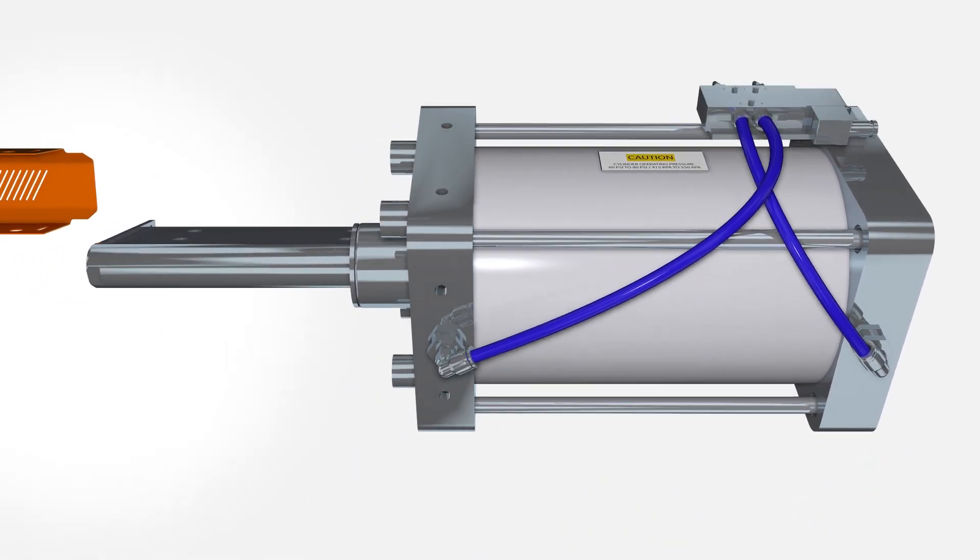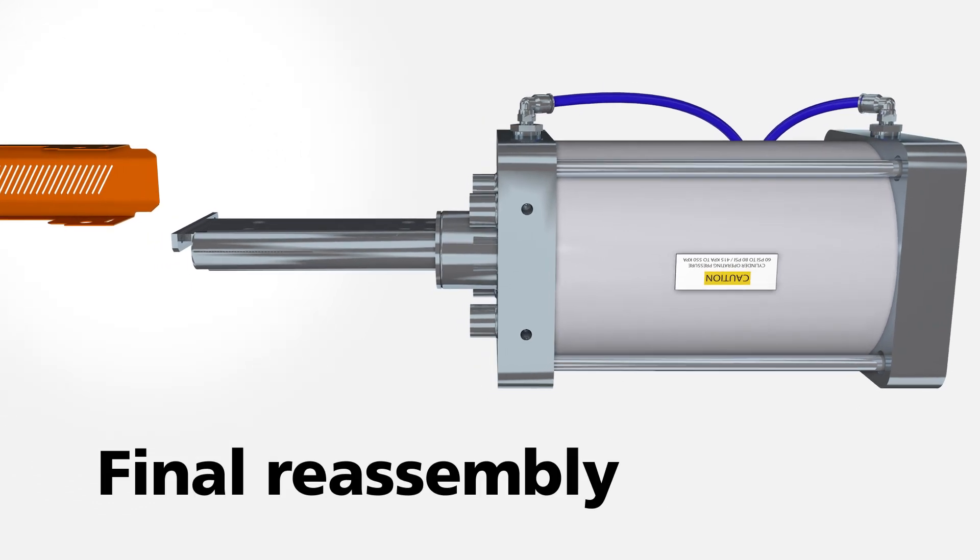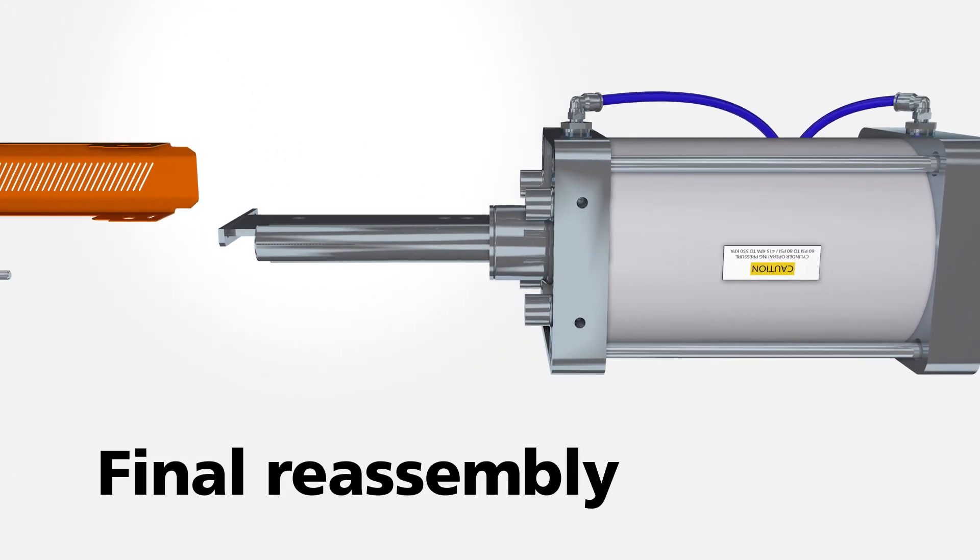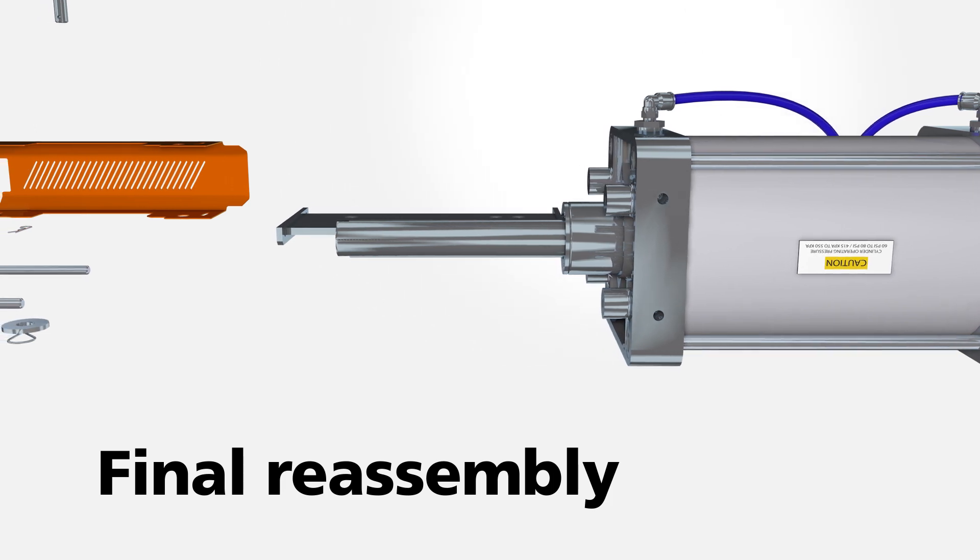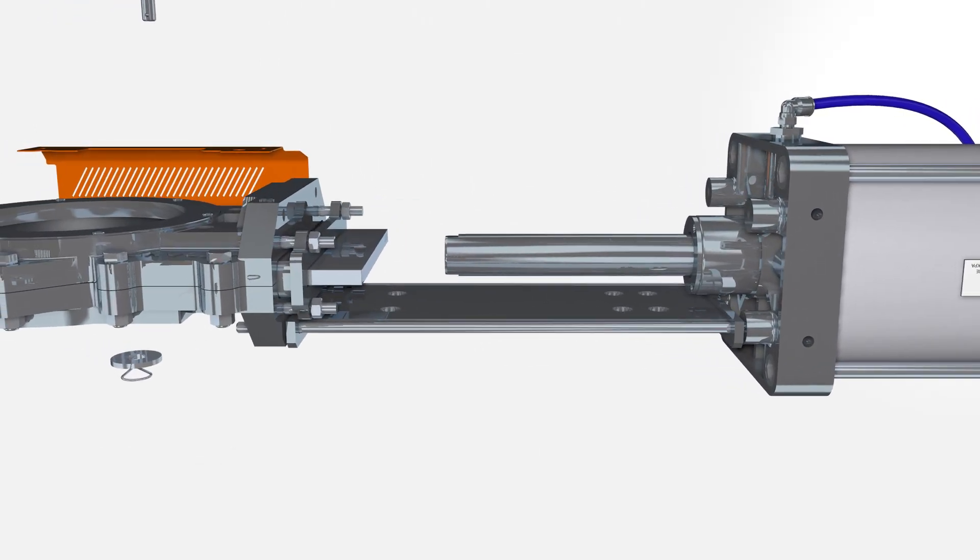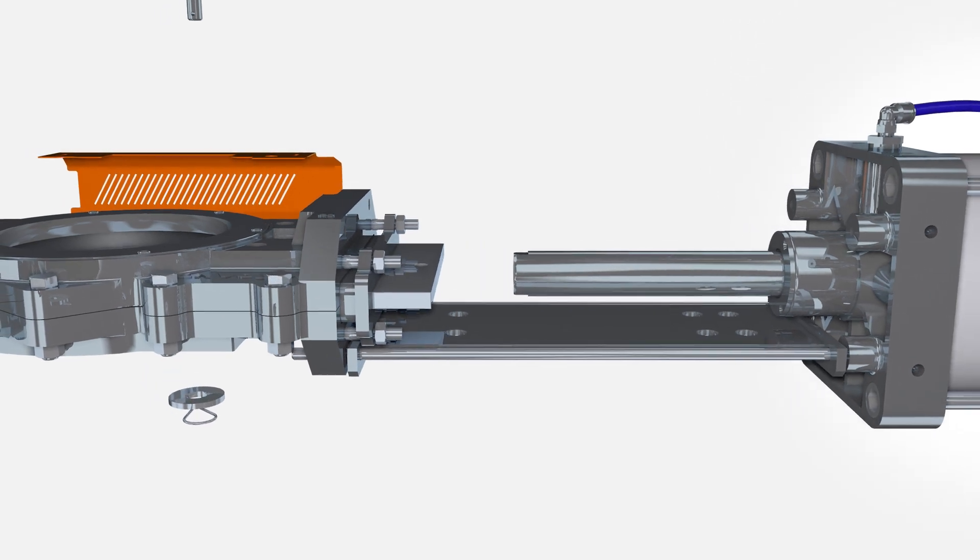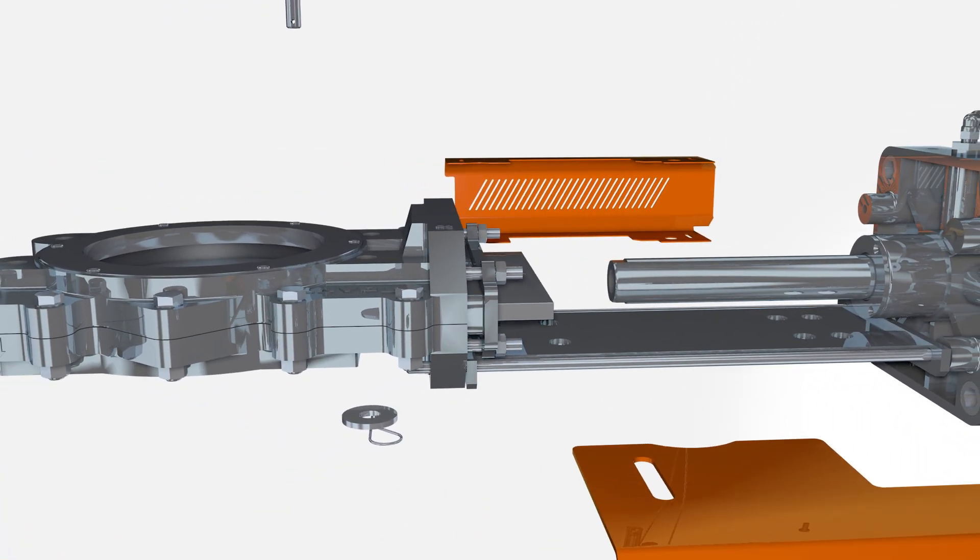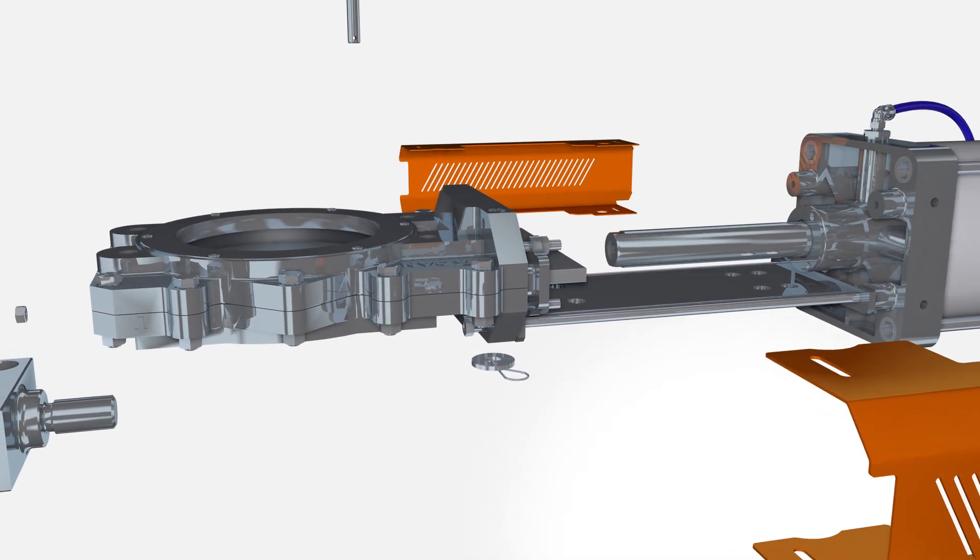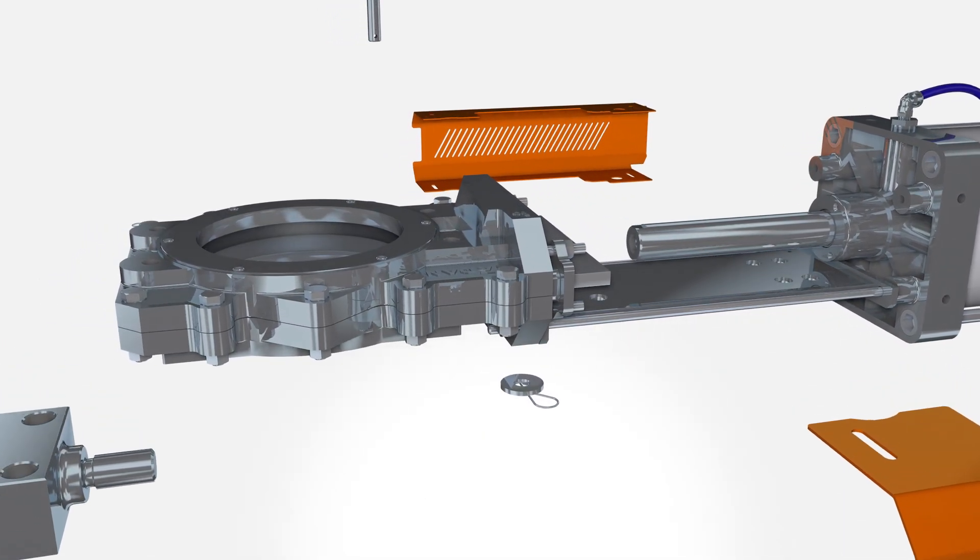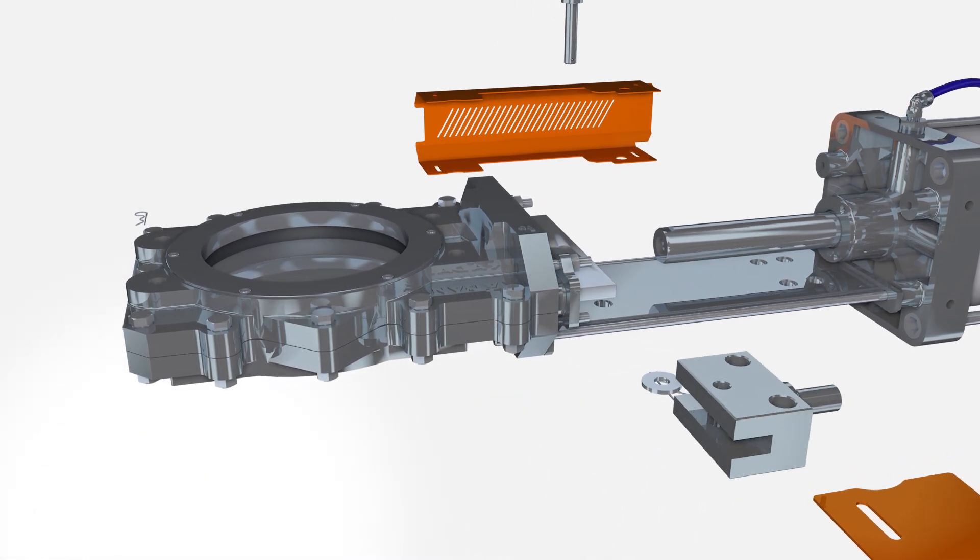Now, let's reconnect the rebuilt cylinder to the transition support and rebuilt valve gate. Reattach the lower transition plate to the cylinder and the valve gate with the two lower tension rod transition beams. Apply anti-seize lubricant to all threads and attach the two hex nuts to the lower transition beams. Reconnect the clevis to the valve gate and piston rod.